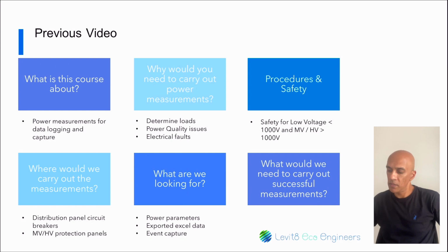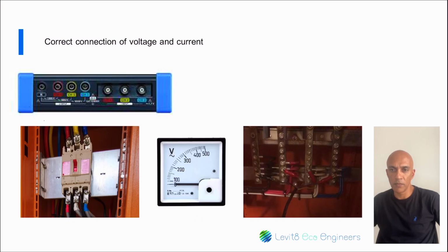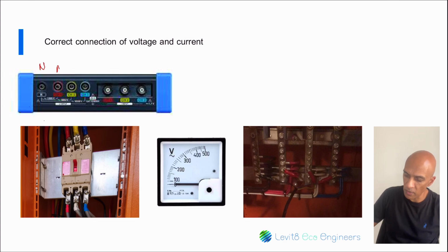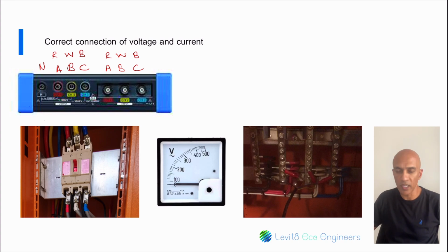Here's a photo of a typical instrument, the terminals of a typical instrument. Now, your instrument will be equipped with three-phase voltage and current inputs. The voltages will be A, B, C, and neutral, and the currents will be A, B, C. So on this instrument, we have neutral, and we have phase A, B, C, and here we have currents phase A, B, and C. In South Africa, we normally have phase colors red, white, and blue, and here red, white, and blue. But it depends on your country and what color scheme your country uses.